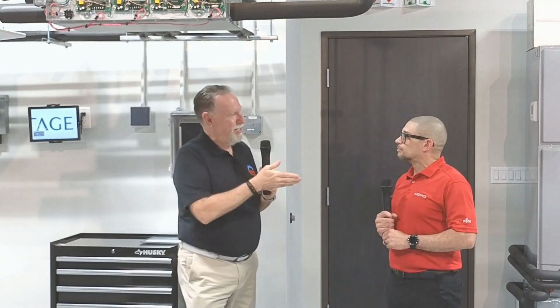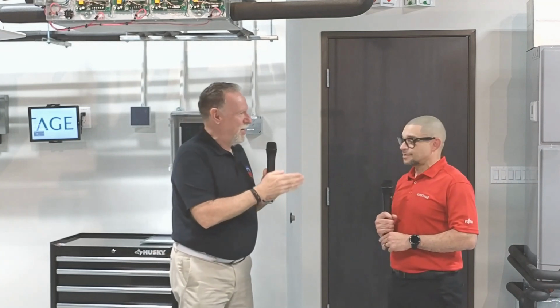The way I explain that to my students: look at your circuit breaker panel. You might have a 200 amp service, but that doesn't mean you only have 200 amps worth of breakers in the panel. Not every appliance or light is on at the same time, so you might have 300 or 400 amps worth of breakers but you're not using them all at once. That's the concept of managing indoor units—not every indoor unit is taking care of a space that requires maximum capacity.